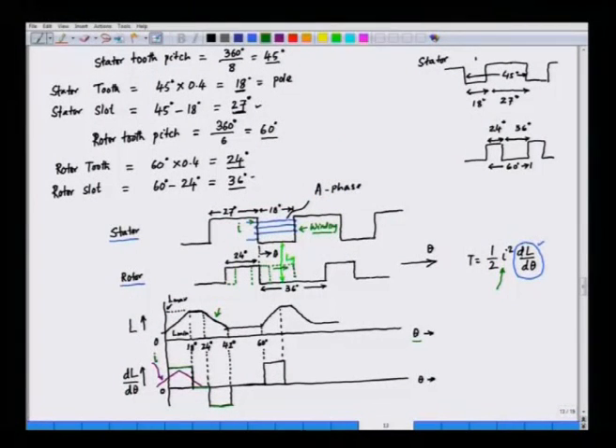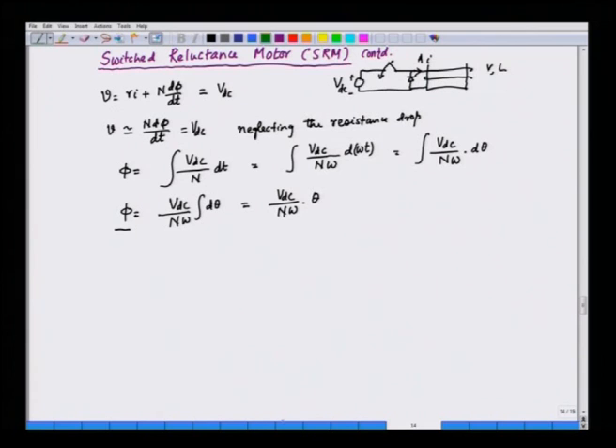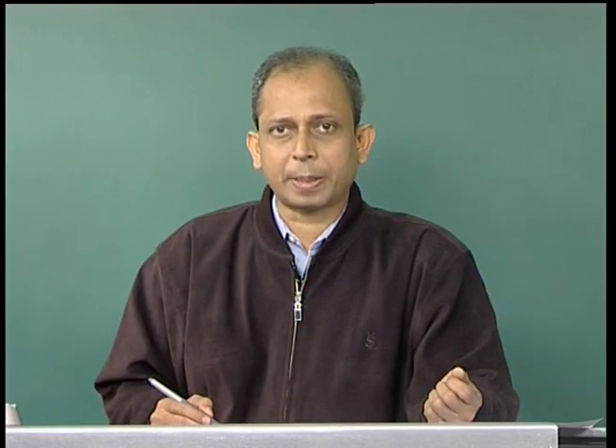If we plot dL/dθ, it alternately becomes positive, then zero, then negative (for example, from 42° to 60° is the minimum inductance region, then the next pole comes under the stator). This is a periodic waveform and dL/dθ is also periodic with rotor angle θ. We control the current so it only exists during positive dL/dθ, achieved by switching a voltage onto the winding using power switches.